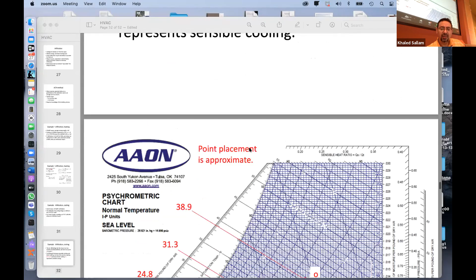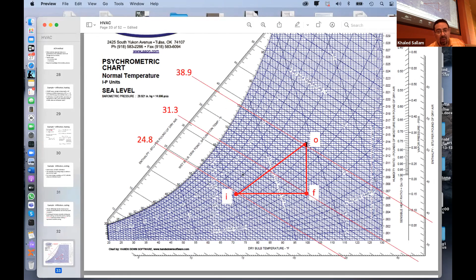So this would be the latent load, and this would be the sensible load. Make sense? So if I establish this point, because he said it's 99 and 75, okay, and for the inside room he said this and this, or maybe this and the humidity ratio. Once you establish those 2 points, you can read the H here. This is the H, you see that? And you can read this H, and then vertically and horizontally you intersect here, and that would be the H.